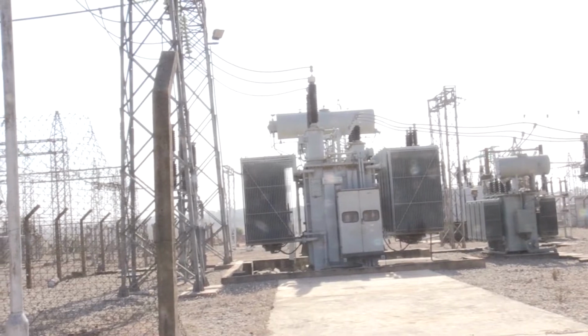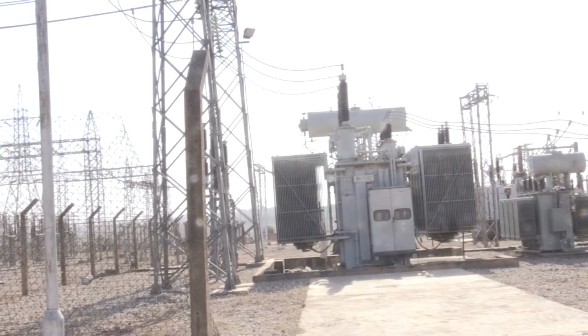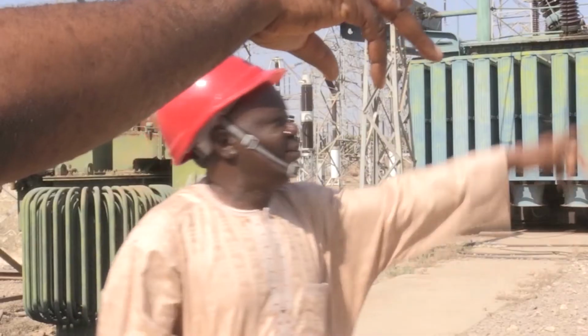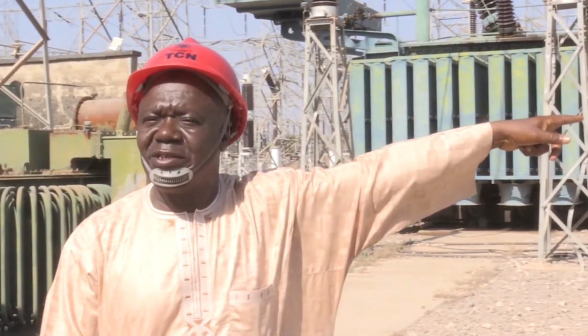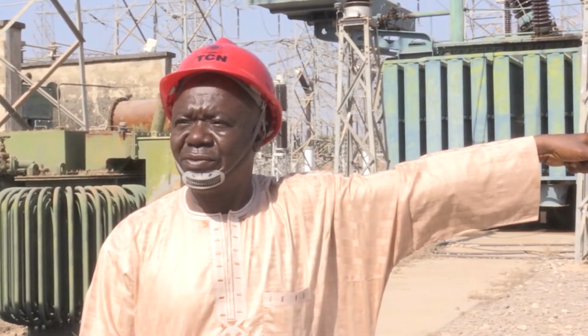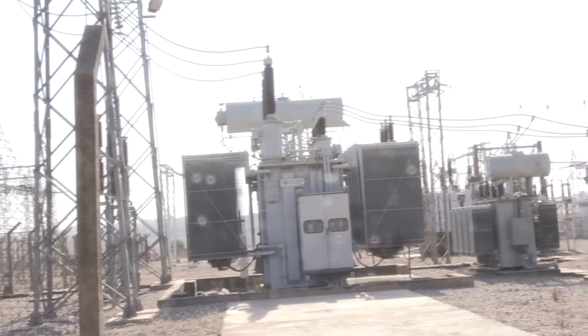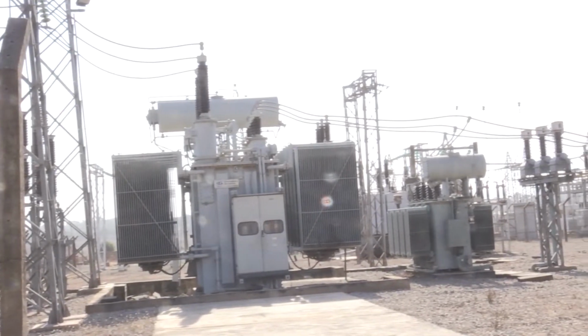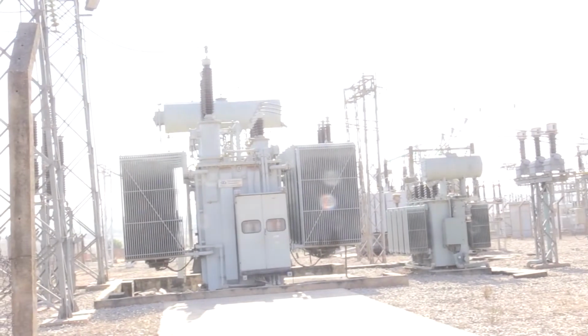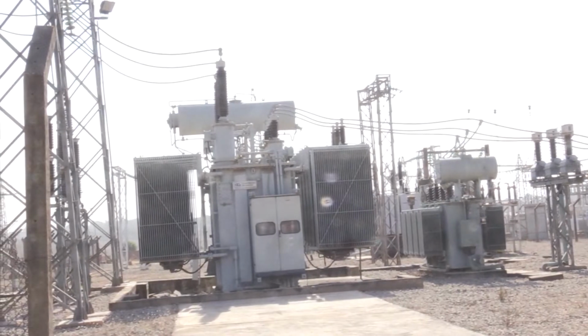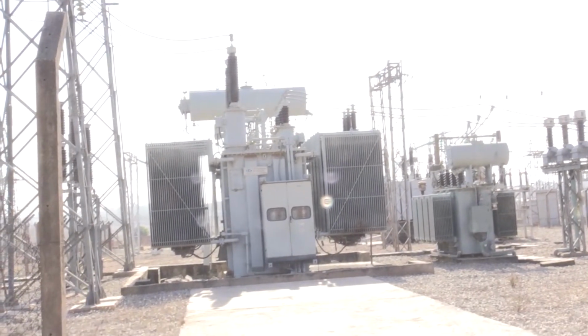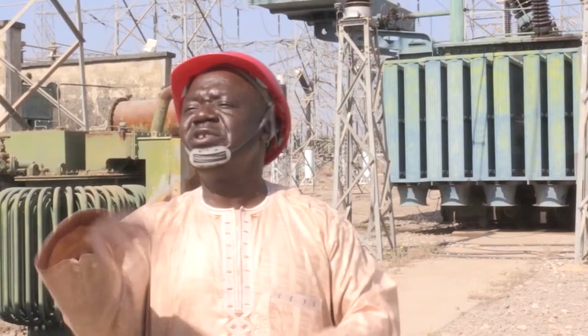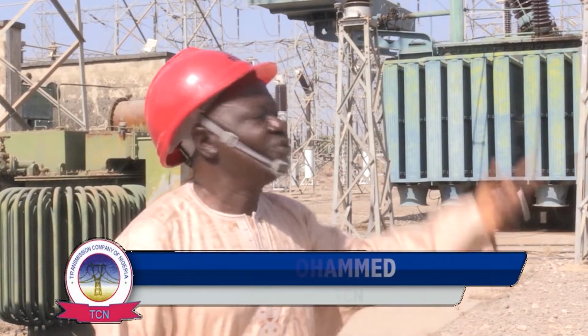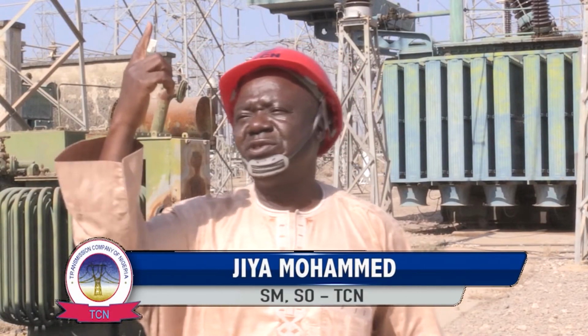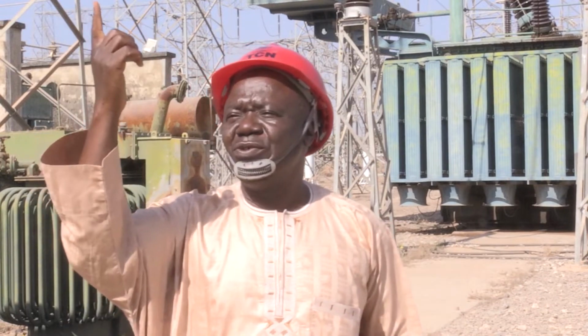There is also a high-capacity reactor at the Mando Mega Transmission Substation. This is a 75 MVAR reactor. The work of it is to suppress the voltage. If the system voltage is very high, we bring in the reactor to suppress the voltage, so as to have a quality voltage to the consumers. But if the system voltage is getting lower, we remove it, then the voltage will shoot up, so as to have a quality voltage for the consumers.